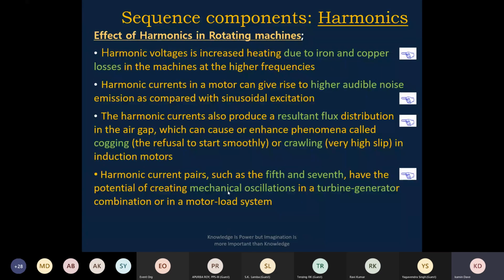Effect of harmonics in rotating machines: so harmonic voltage increases heating due to the iron and copper losses in the machine at higher frequency. Yes, it increases the heating due to the iron and copper losses. Harmonic current in a motor can give rise to high audible noise. Actually, sometimes we see the humming sound if harmonics are significant, the noise, we can see the humming sound or higher audible noise.